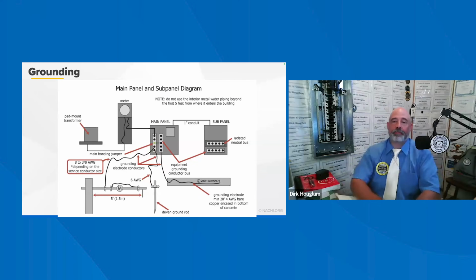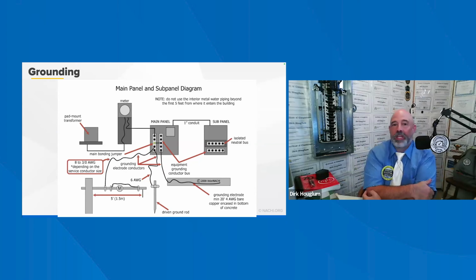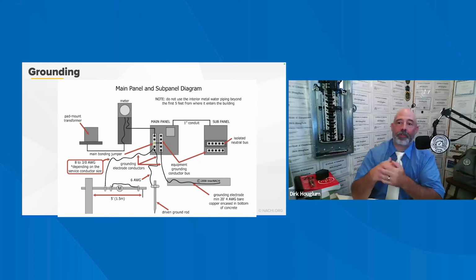Generally speaking, the difference between grounding and bonding is this. Grounding is a direct connection to the earth to aid in removing damaging transient overvoltage due to lightning. Bonding ensures the electrical conductivity of the fault current path, to provide the capacity and ability to safely conduct any fault current likely to be imposed, and to aid in the operation of overcurrent protective devices. Properly bonding all metal parts within an electrical system helps ensure a low impedance fault current path.